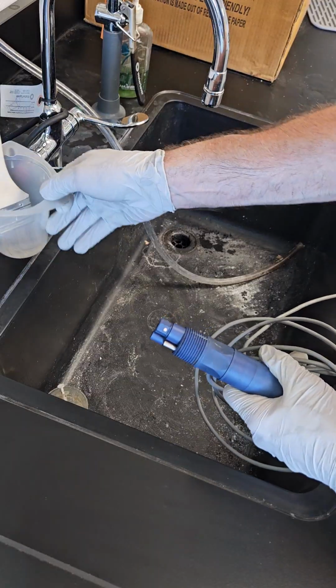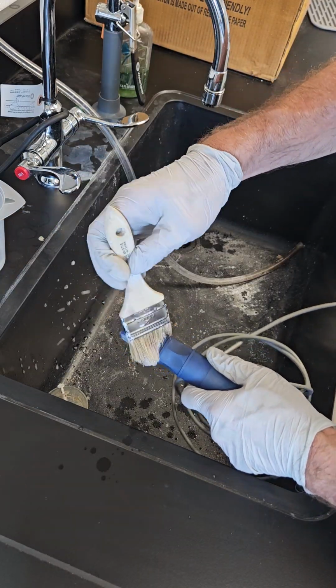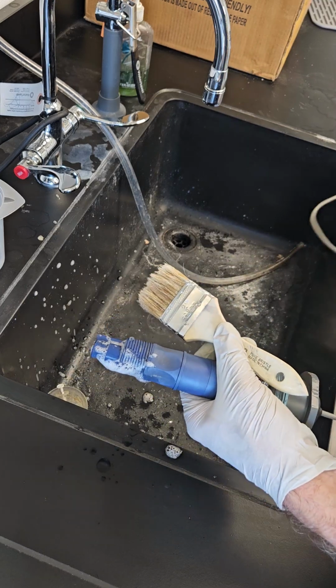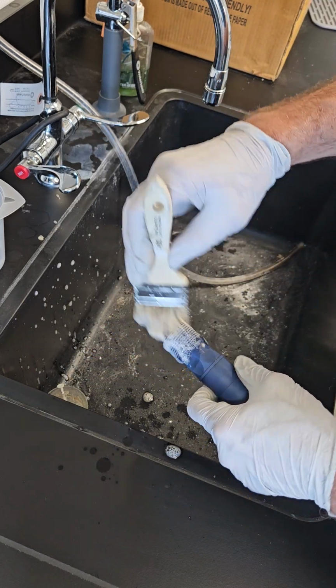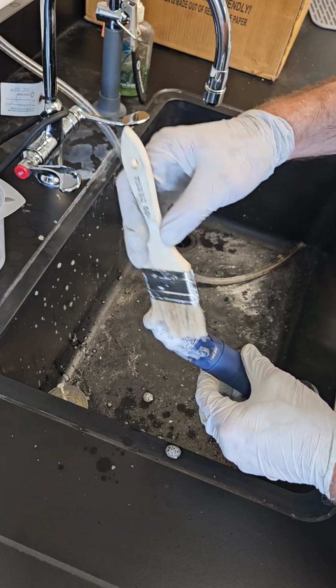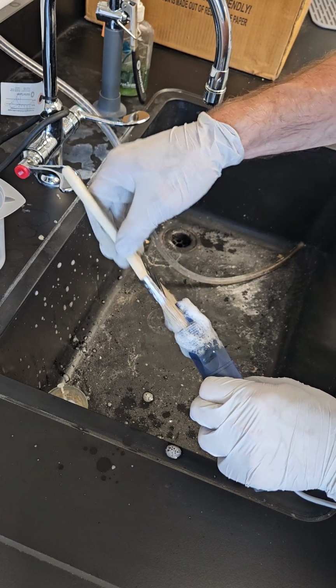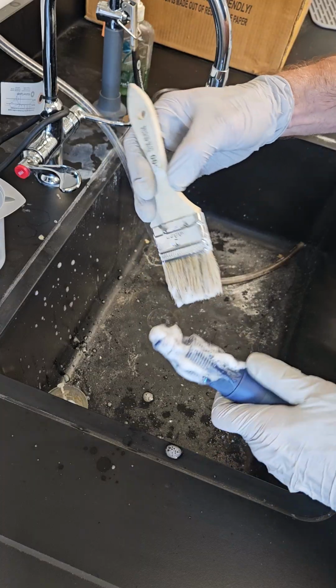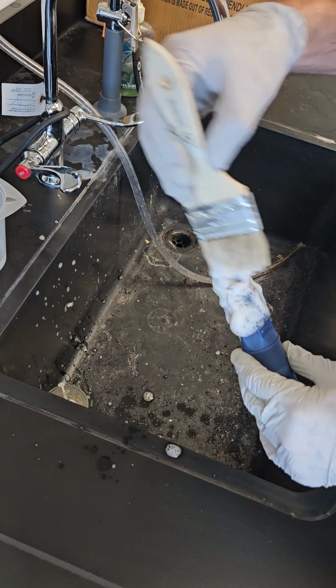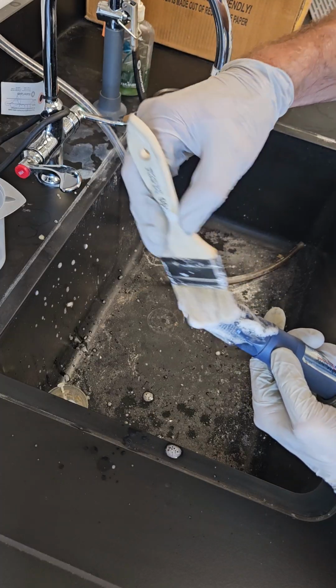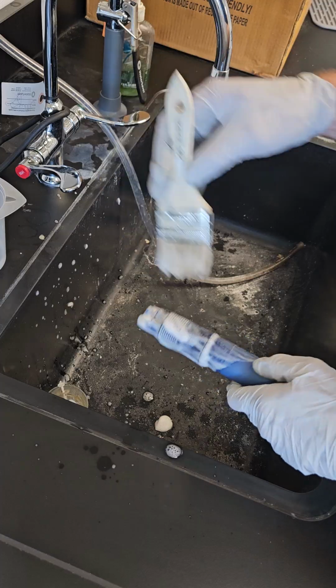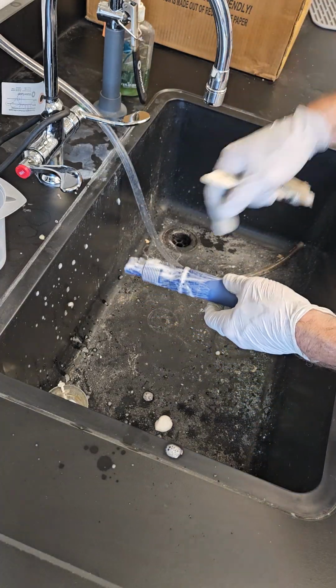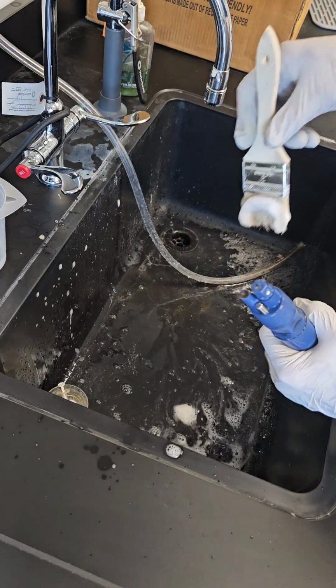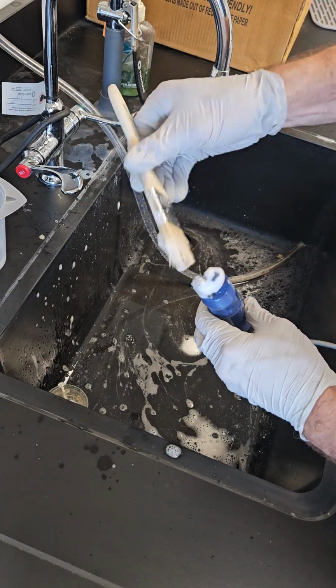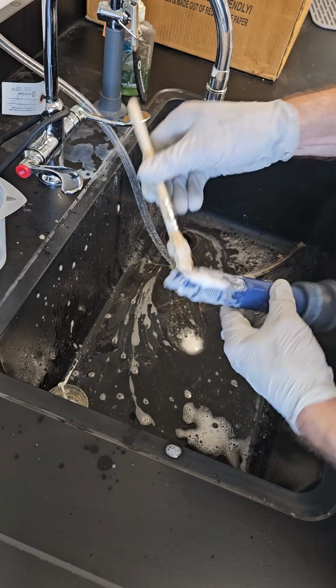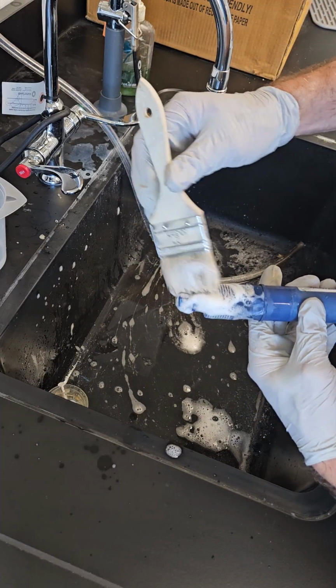So once I have a soapy solution like this, you can see it's a very aggressive soap, the filter clean. So you don't need to use it straight. You can dilute it, maybe 3 to 1 or something. 1/3 soap, 2/3 water. Then use this bristle brush. Careful not to let the metal ferrule hit the crystal, but you can brush that off thoroughly throughout. You can even clean it if it's got a lot of ink on the rest of this when it comes out of a system, and rinse it off thoroughly. But you can do that a couple of times and get that crystal and everything really clean with the filter clean soap.